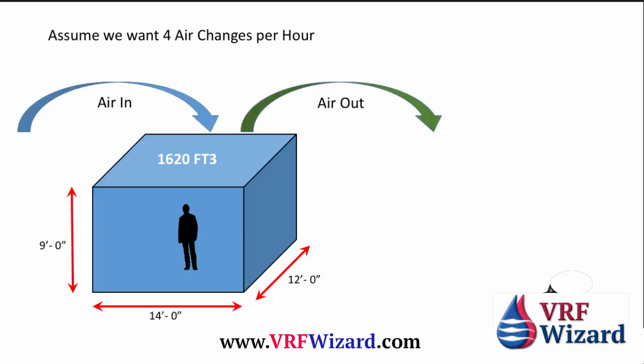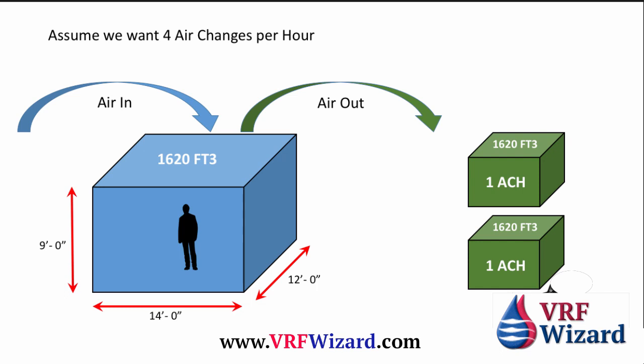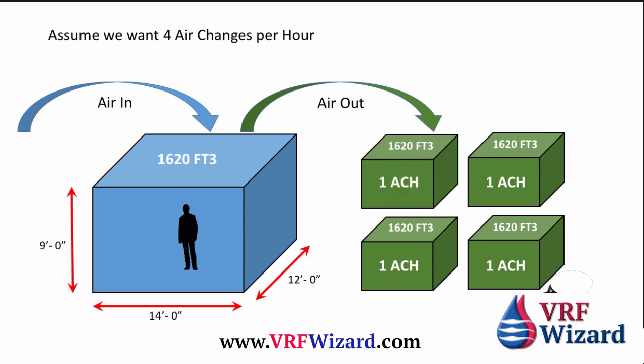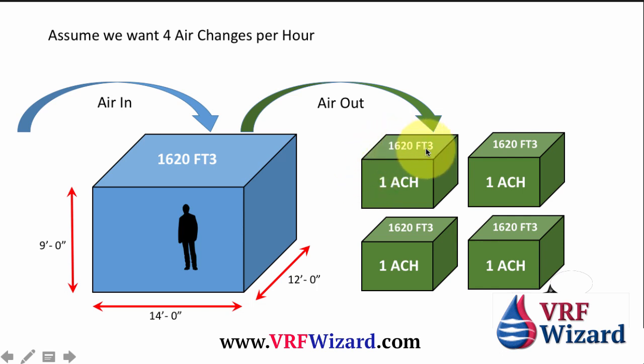Step two: assume we're going to do four air changes. We're going to do this four times in an hour — we're going to remove air out of this room equivalent to four times its volume within an hour. The room volume is 1620 cubic feet for each exchange, because that's the volume of the room. Every time we take out that volume in an hour, that's considered one air change.